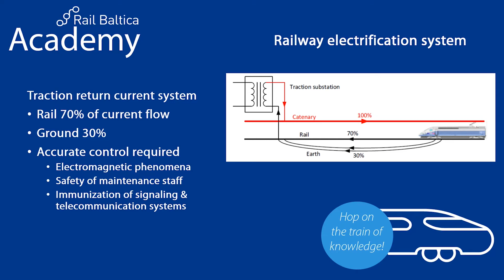Then we have the traction substation. This is the part feeding the overhead catenary system with the required power. It belongs to the railway infrastructure and is connected to the high voltage electrical grid of the country, typically at 110, 220, or 330 kilovolts. A set of transformers steps down from high voltage to medium voltage to deliver the tension needed for electrification, around 25 kV, more precisely between 22 and 28 kilovolts.